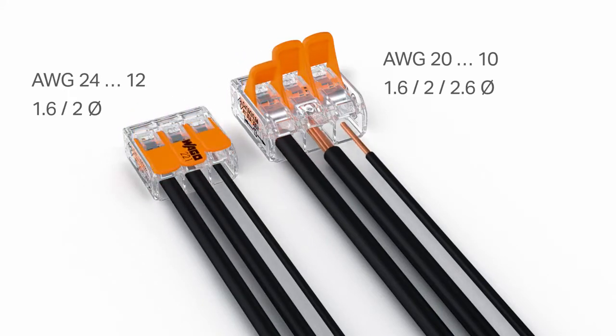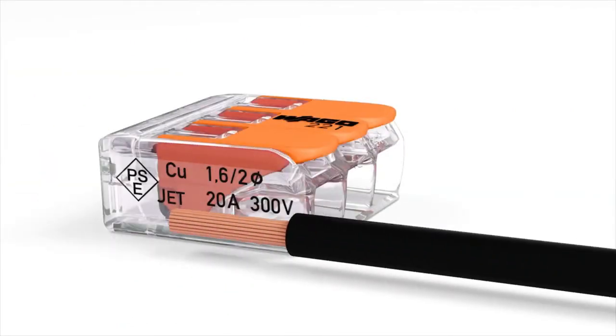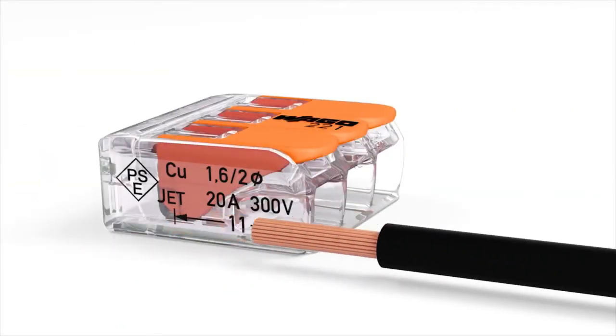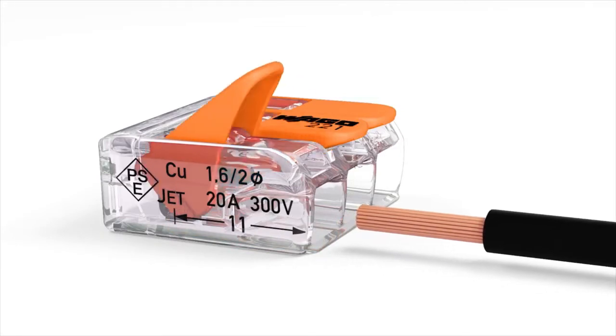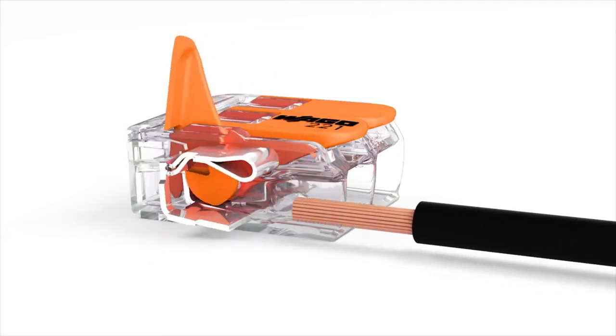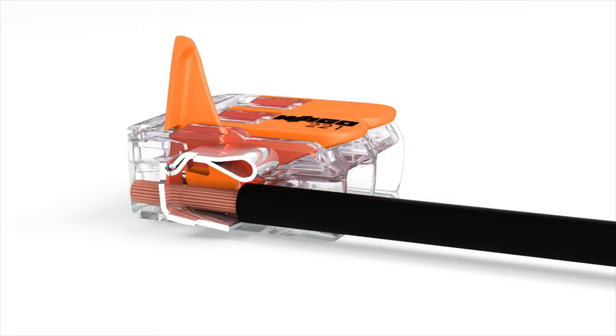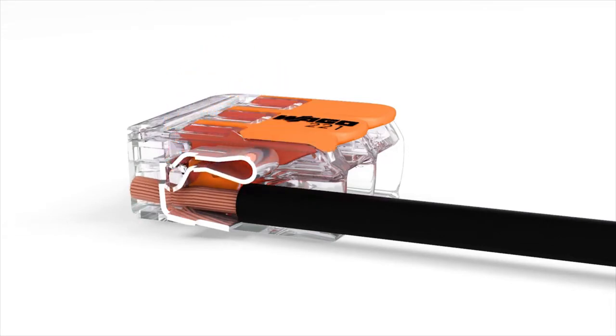Wiring is simple. First, strip the conductor according to the strip-length guide printed on the side of the connector housing. Open the clamping unit via the easy-to-use lever, insert conductor, then simply lower the lever to close the clamp.